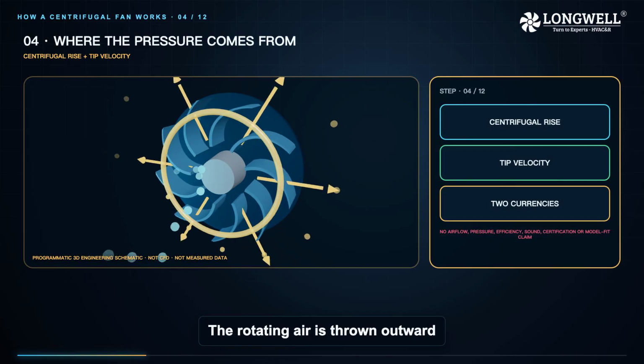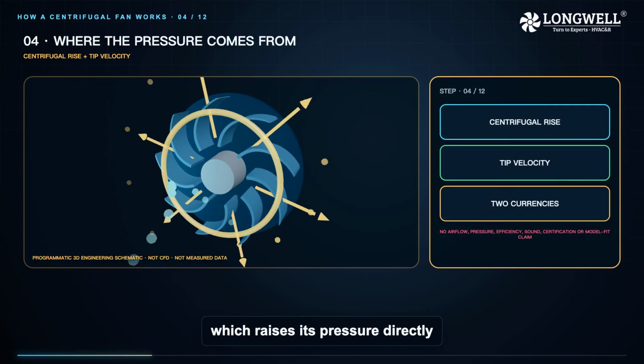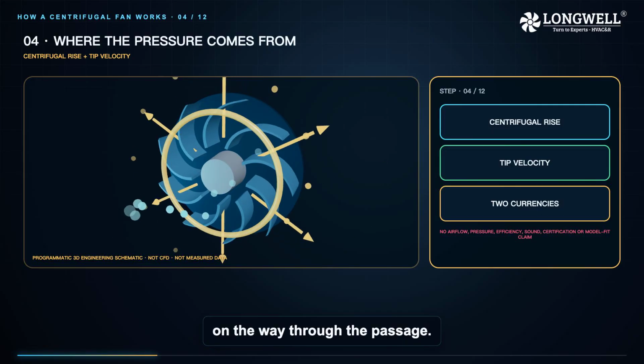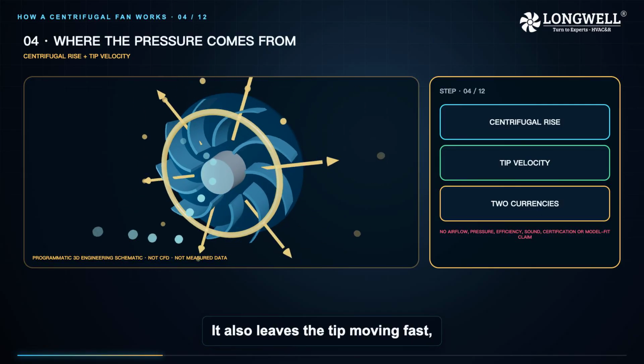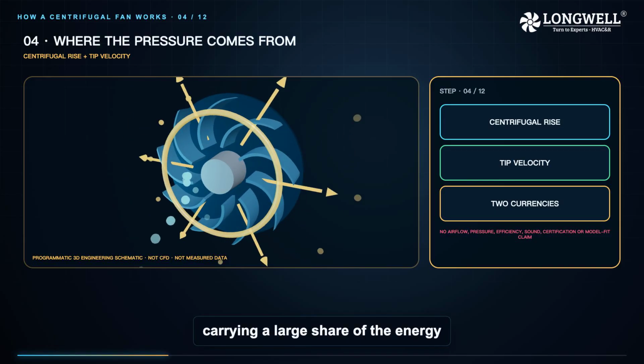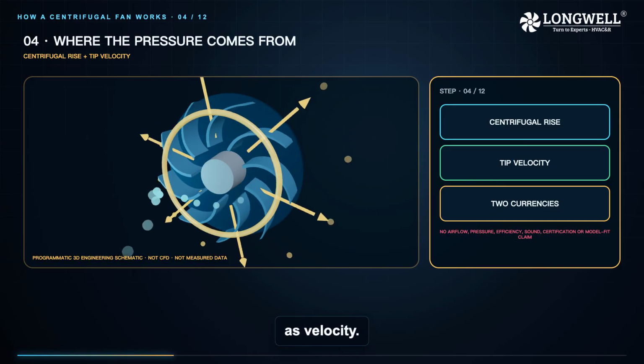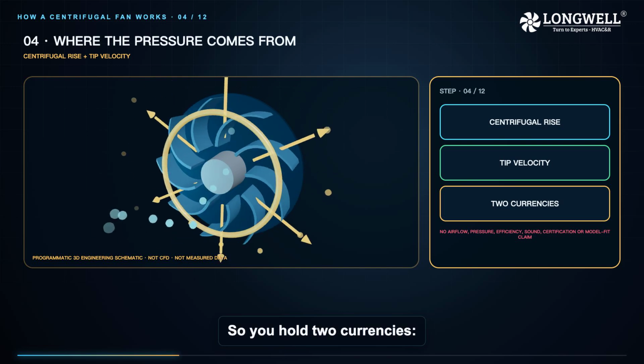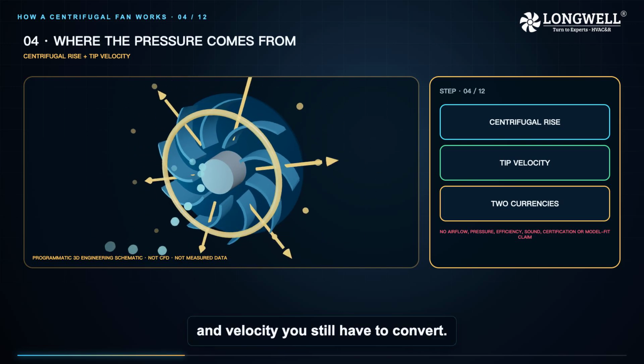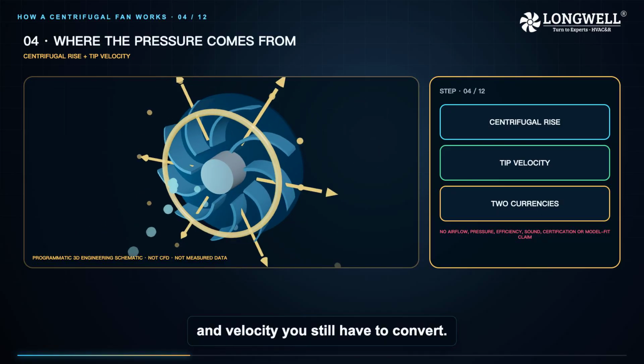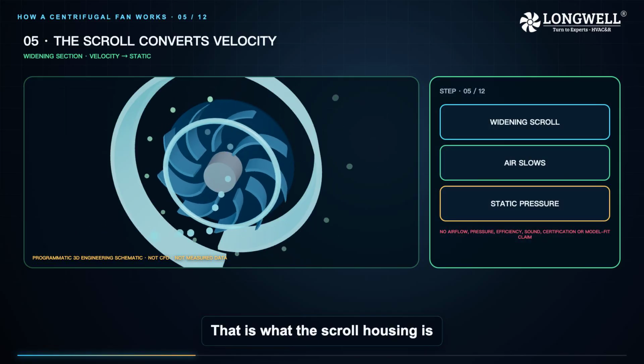The rotating air is thrown outward by centrifugal effect, which raises its pressure directly on the way through the passage. It also leaves the tip moving fast, carrying a large share of the energy as velocity. So you hold two currencies, pressure you already have, and velocity you still have to convert. That is what the scroll housing is for.